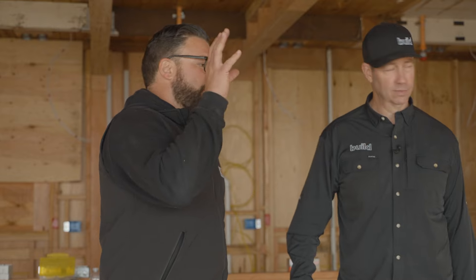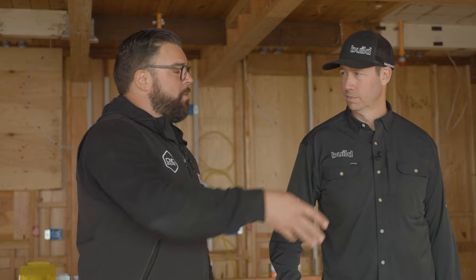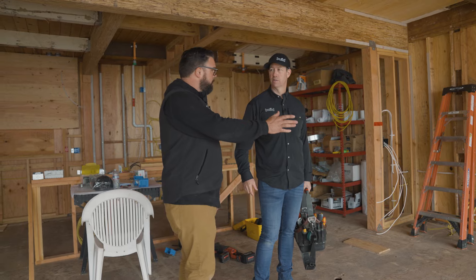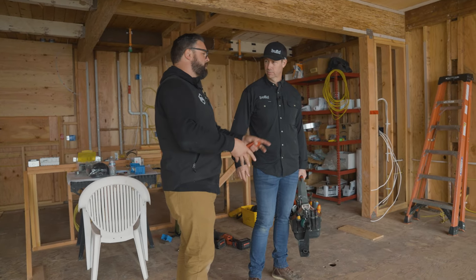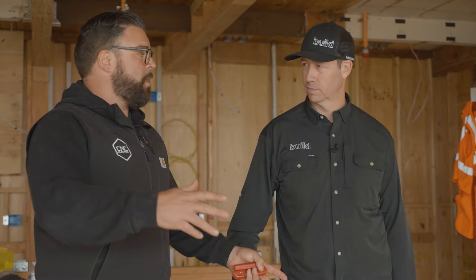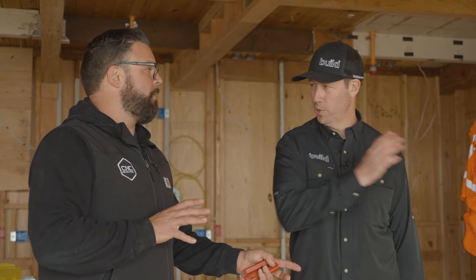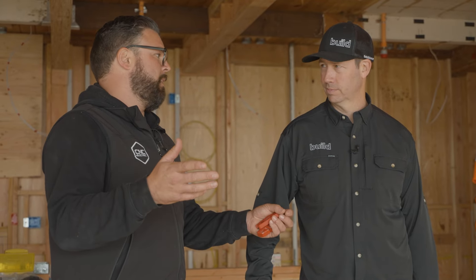I'm going to show you how to wire a receptacle. It's at the stage right now where we're getting ready for closing. What we do is strip out and make up our receptacles — meaning we strip the wires and make the connections now. During rough-in, all our wires are nicely tucked in the box, and the mess from cutting happens during rough. After drywall and finish comes in, that's when we come back and trim out — very little mess.